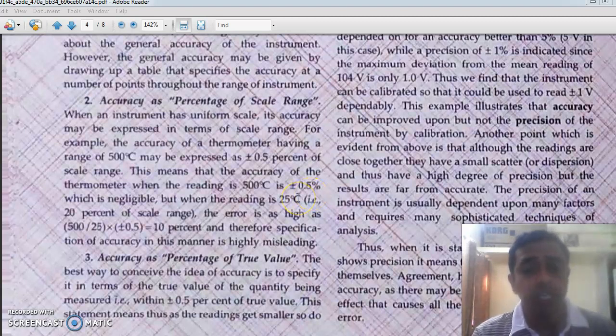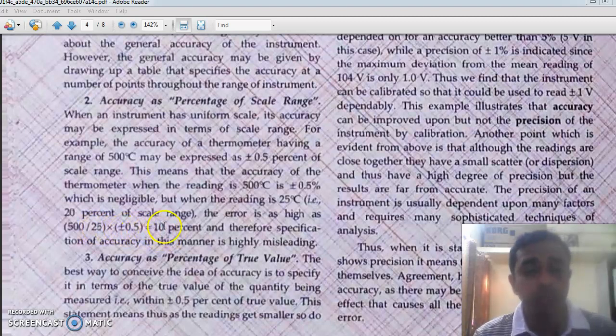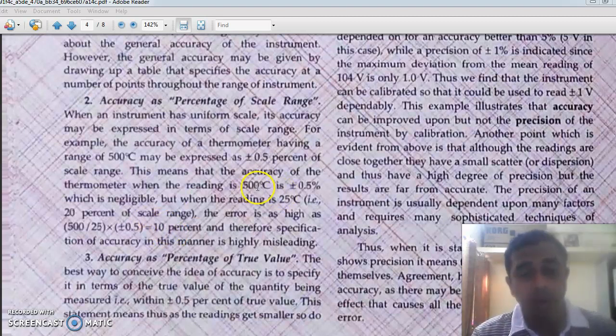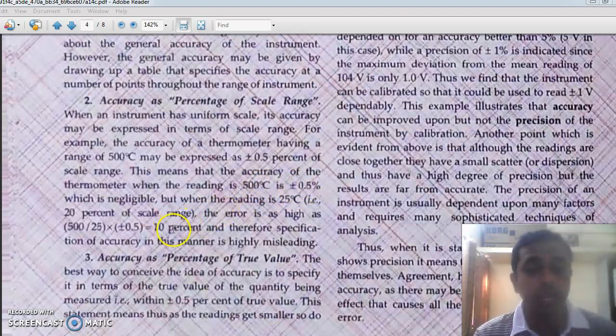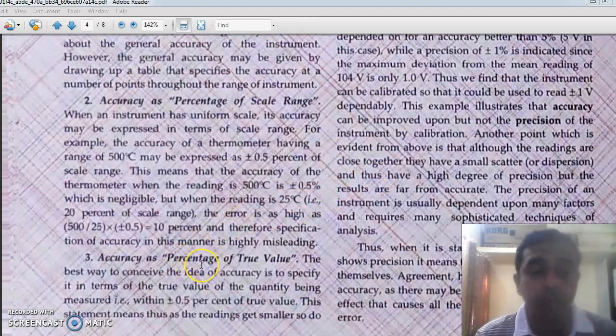But when the reading reduces — suppose we are measuring a temperature of 25 degrees Celsius — the percentage error is 10 percent. So when the reading is very high the error is very small, but when the reading comes down the error is very large. This is highly misleading, so we never specify accuracy as percentage of scale range.